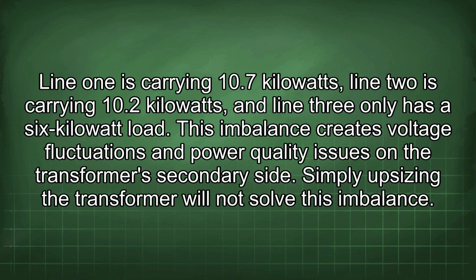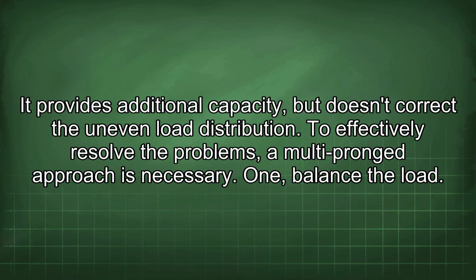This imbalance creates voltage fluctuations and power quality issues on the transformer's secondary side. Simply upsizing the transformer will not solve this imbalance. It provides additional capacity, but doesn't correct the uneven load distribution. To effectively resolve the problems, a multi-pronged approach is necessary.